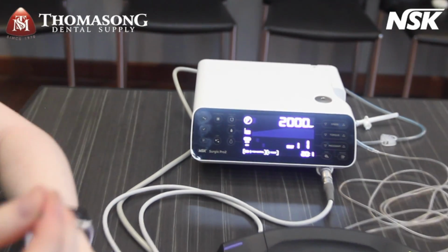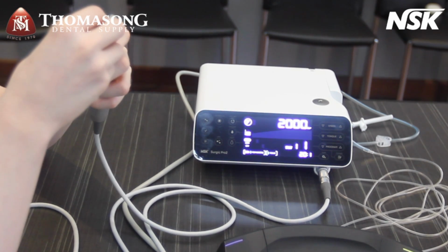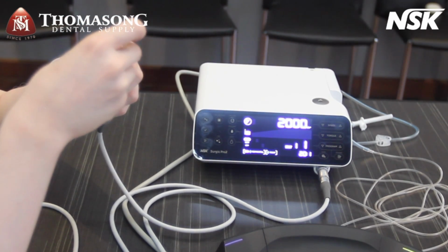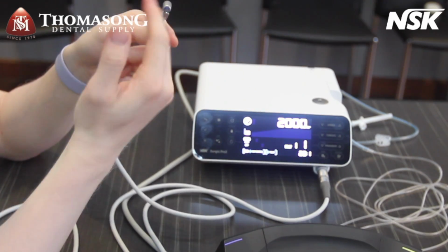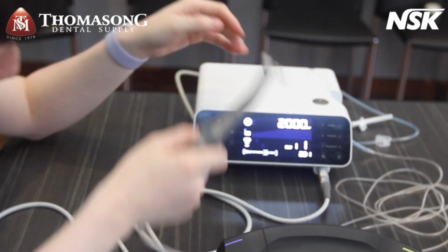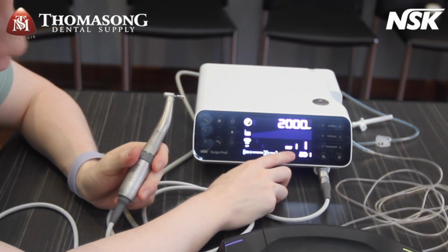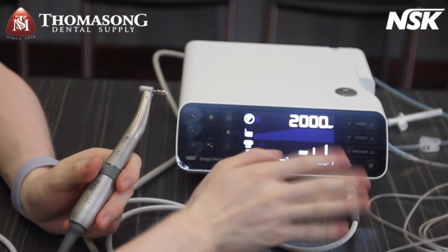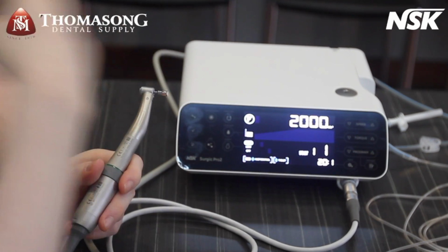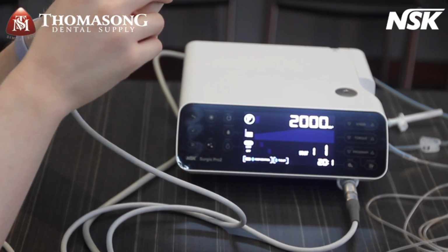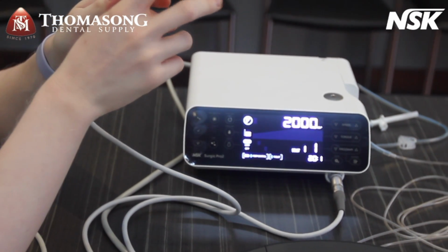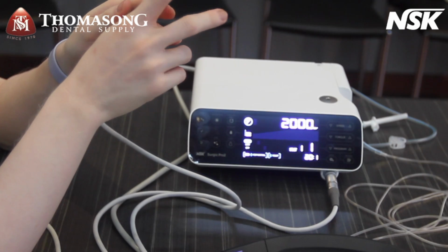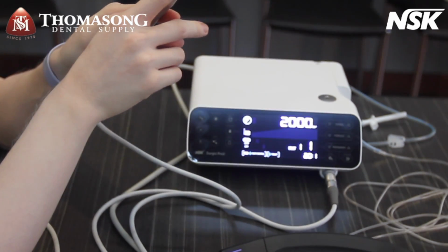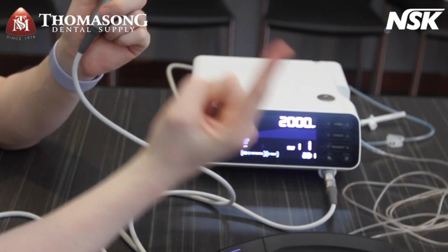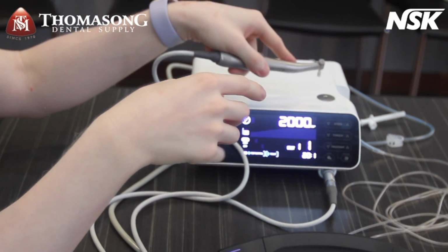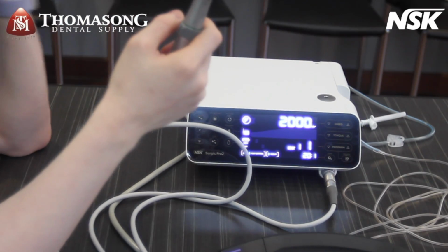There's the calibration burr also, the last feature on the show. There are 3 steps of calibration. You need to put it in like that, and the new burrs are shorter now. Make sure it's at 20:1. That's for the calibration to take place. But basically adjust that to your handpiece, right? The only one where you need the calibration burr is the 20:1. There are 3 steps: torque calibration without load, torque calibration with load, where you actually put it in, and then speed calibration. You would not put this in again.